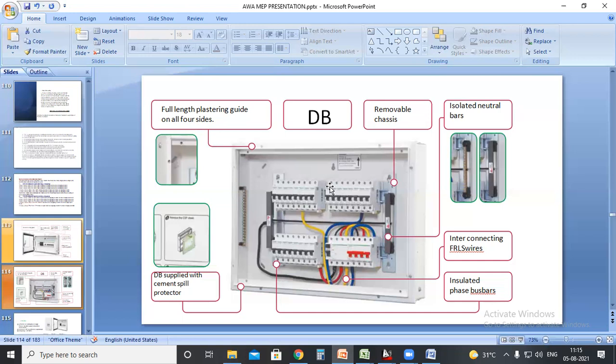To get the 415 volt, you need both the three phases together. But here it is split. That means you are getting three-phase supply at the incomer, but it is actually split into 230 volt, which means if I am taking a wire from this particular breaker, I would get 230 volt only. What does that mean? Even if you are taking the three-phase distribution board, that is the TPN distribution board, all equipment connected in this particular DB will have 230 volt only.